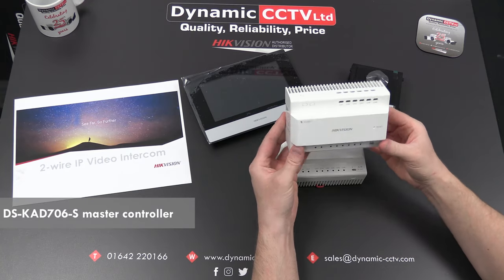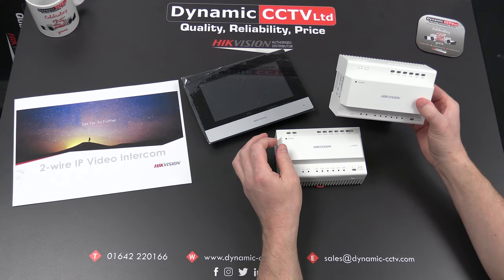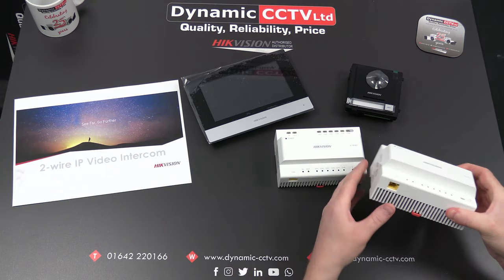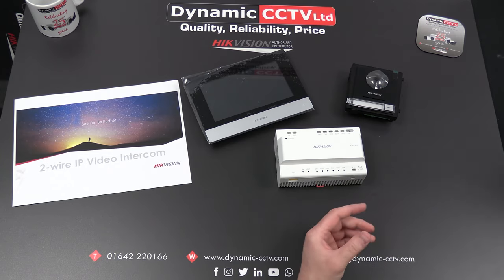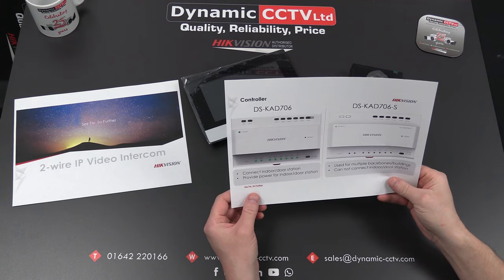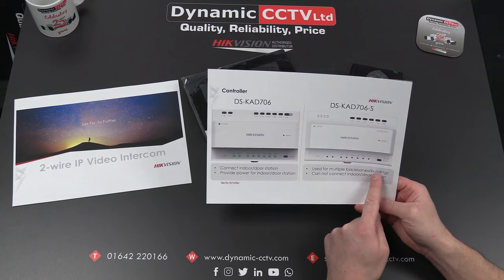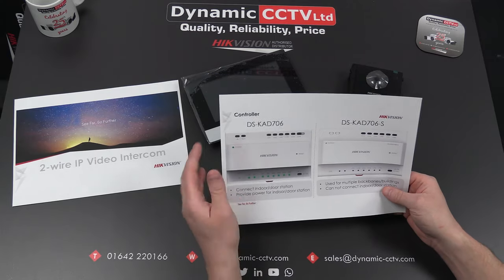That additional controller is the DS-KAD706-S. It looks almost identical to the DS-KAD706 but is designed only to have DSKD706s or additional KD706s connected to it. It also has a network connection, so when backbones are linked you still have the ability to connect to the network, which allows intercom connectivity to back-end VMS, NVRs, and mobile phones. The DS-KAD706 is for connecting indoor and outdoor stations, powering and linking them, while the DS-KAD706-S is for connecting multiple backbones and buildings, and cannot be connected to indoor or outdoor stations directly — something to bear in mind when planning your system.